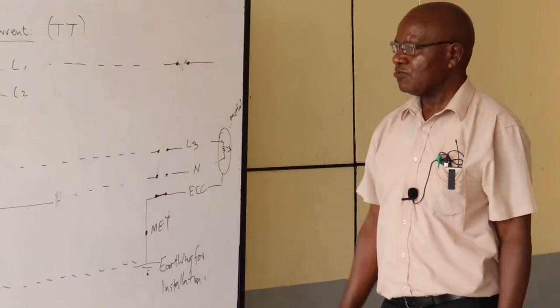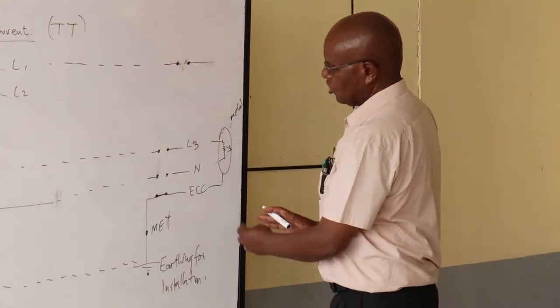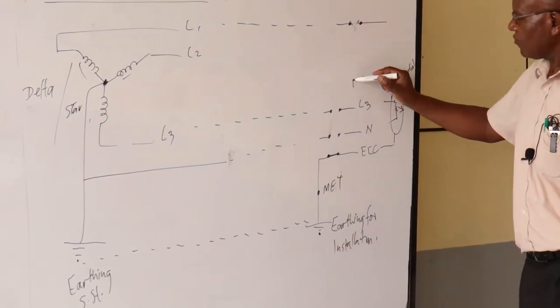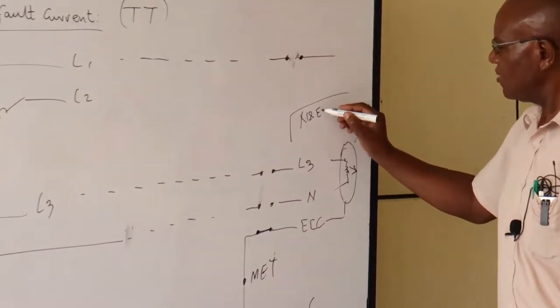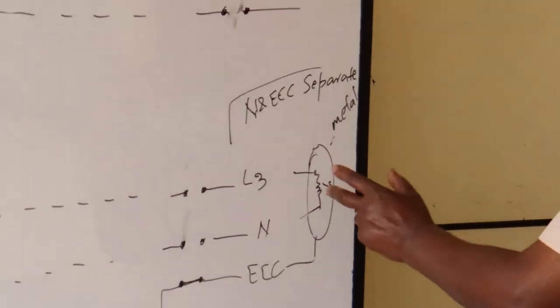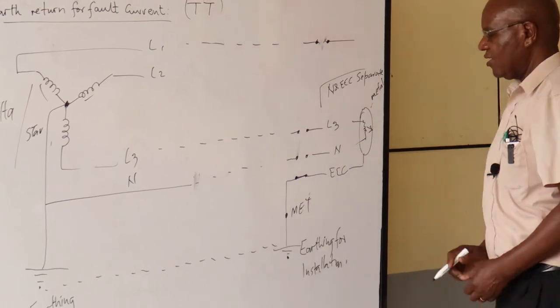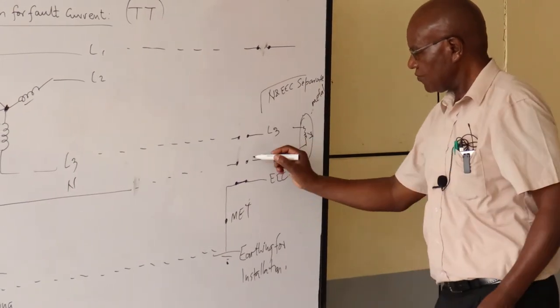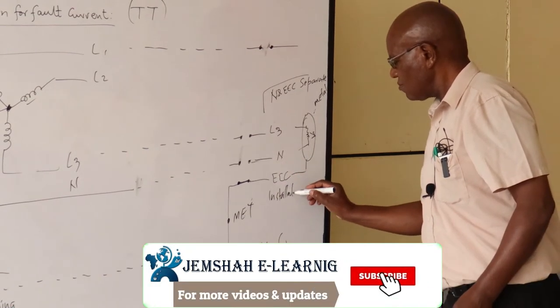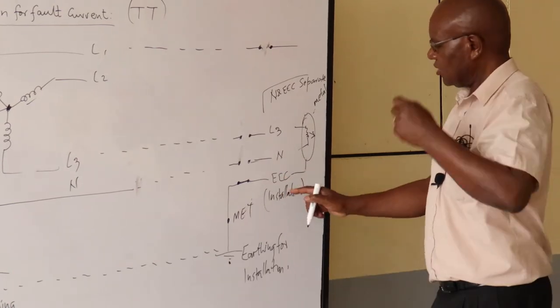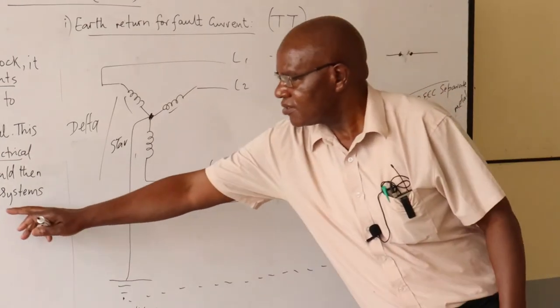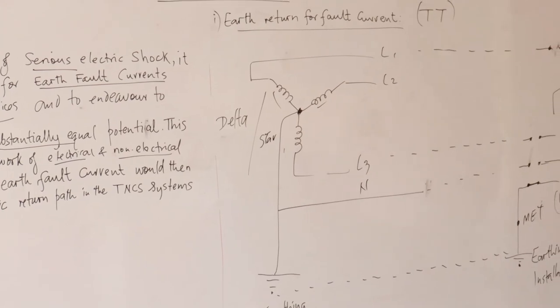On the installation side, although both the neutral and the ECC are earthed, inside the installation they should be separate — they should not touch. The neutral here is connected to the ground at the substation, and the ECC is connected to the ground at the installation. One of the IEE recommendations is that once inside the installation, the ECC and the neutral should be kept separate.